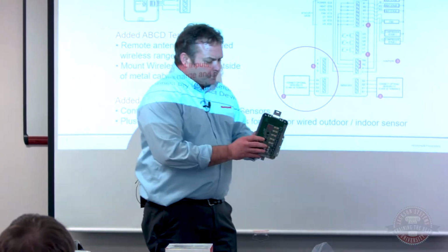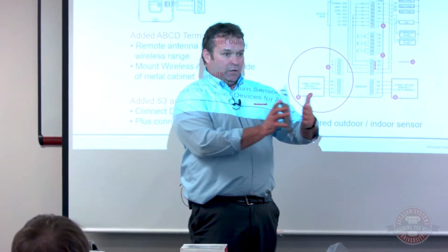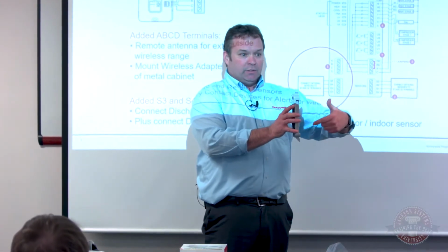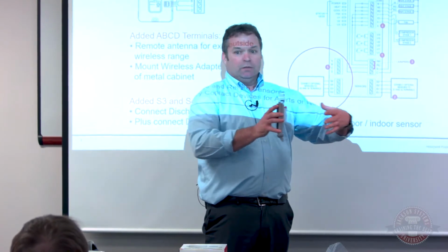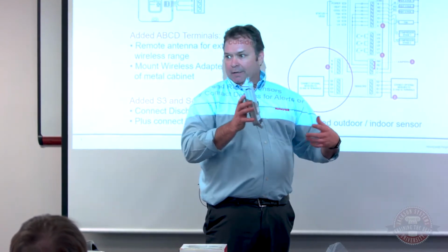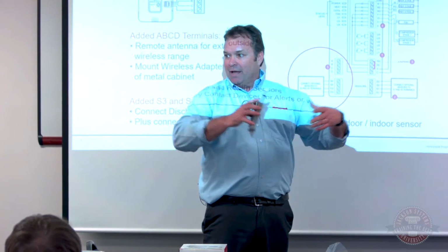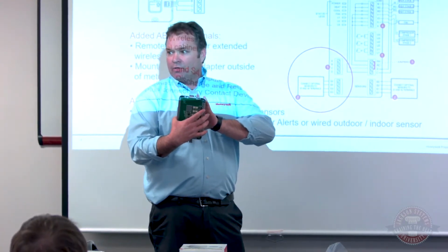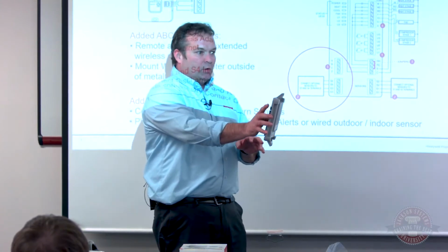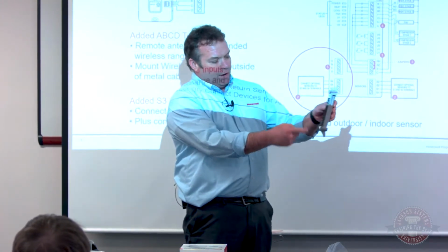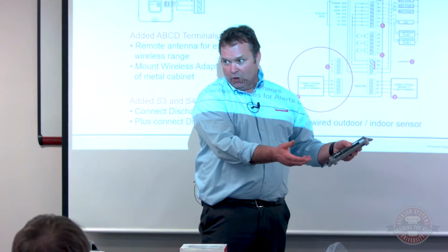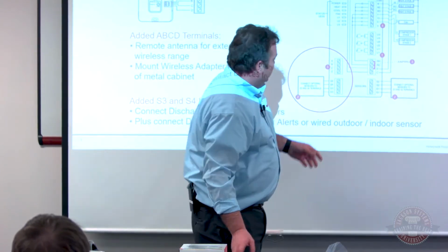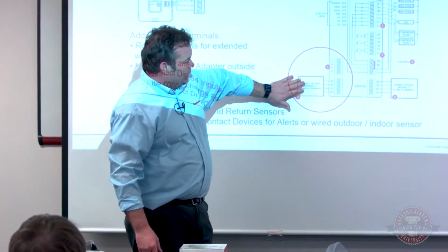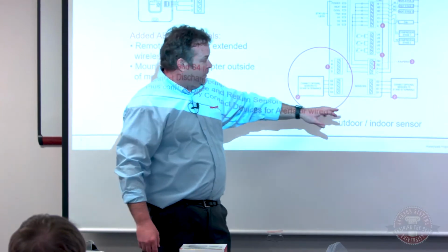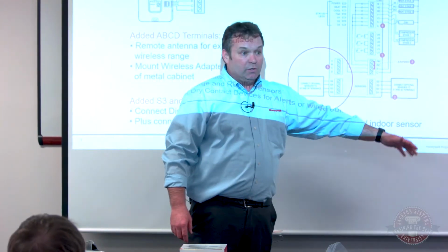The board that mounts down at your equipment is where all the wiring takes place. You don't want to put that directly on the side of the furnace where the motor is, because you don't want to get some harmonic magnetic field around it. So usually people will mount it on the duct drop or on the wall beside the equipment, and you bring in your wire from your furnace board to it—that's really all the wiring you need. Then you can add your S terminals for your supply and return sensor, or a float switch, whatever you want.